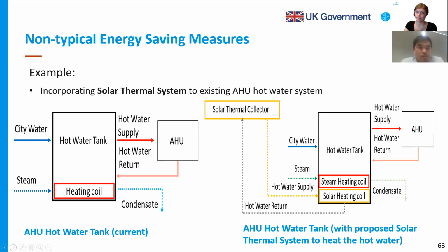As a non-typical energy saving measure, also previously mentioned by Karthik, there is the solar thermal system. Here, I want to explain one example of implementing a solar thermal system in the AHU reheat hot water system. In the current situation, the hot water to the air handler is heated by steam supplied from the boiler, and the requirement is only 80 to 90 degrees C. This can easily be compensated by a solar thermal system as a hybrid system for the hot water tank to the air handler reheat system.